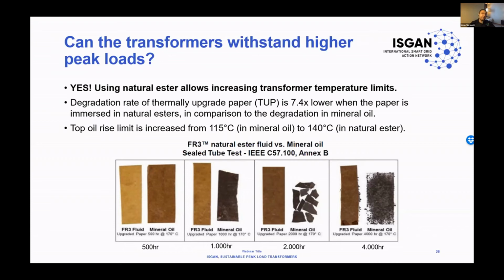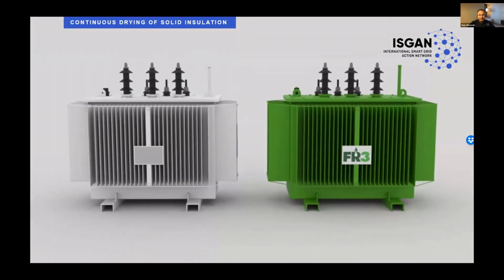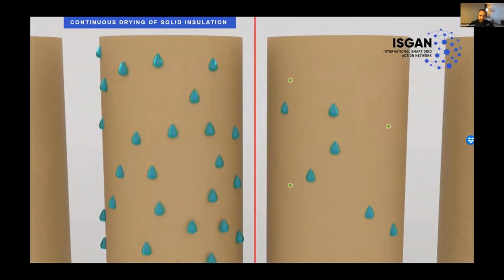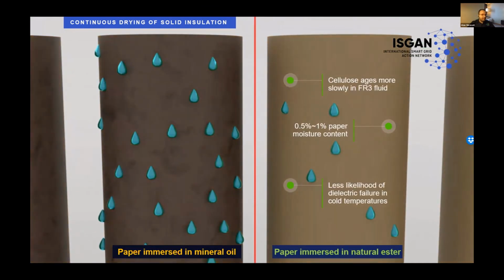Then they started investigating what is behind it. Fernando, if you could move to the next slide, please. And the reason is all about water. We know that when cellulose degrades, it generates water as a byproduct. And this water remains impregnated in the paper, generating more degradation. And then more degradation generates more water that generates more degradation. This is what happens when the paper is immersed in mineral oil. Conversely, when the paper is immersed in natural ester, the water that is generated by the paper degradation migrates from the paper to the oil and is consumed by the natural ester.